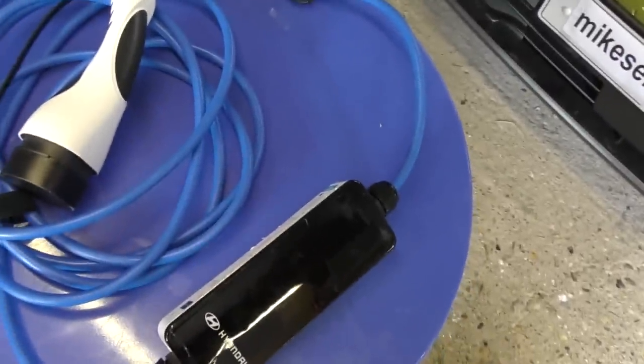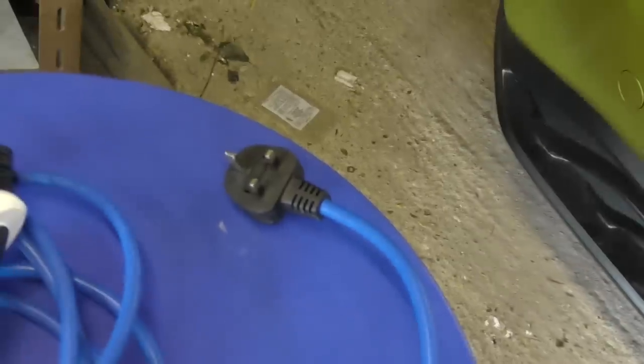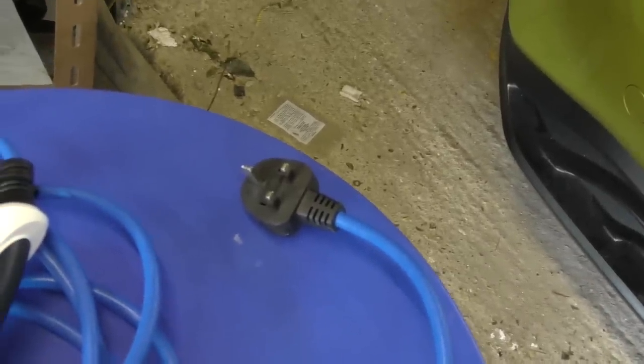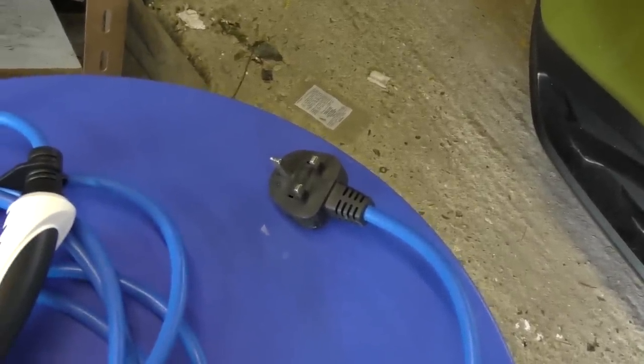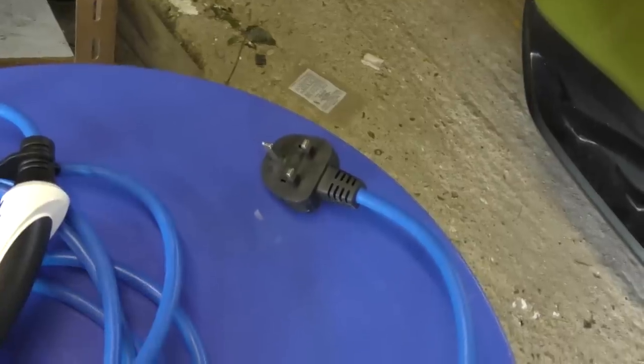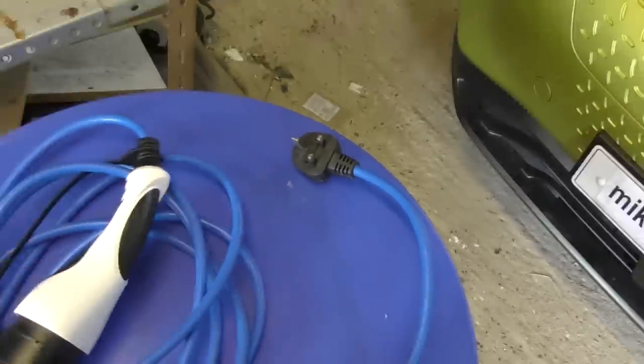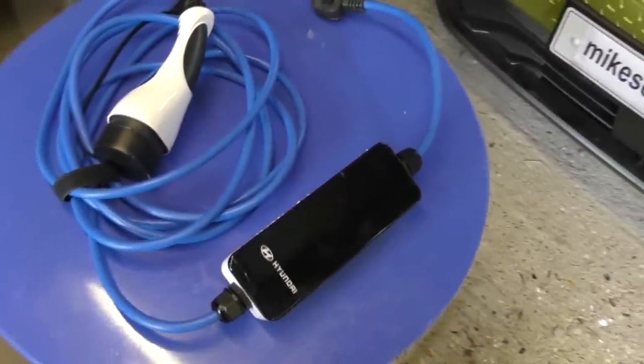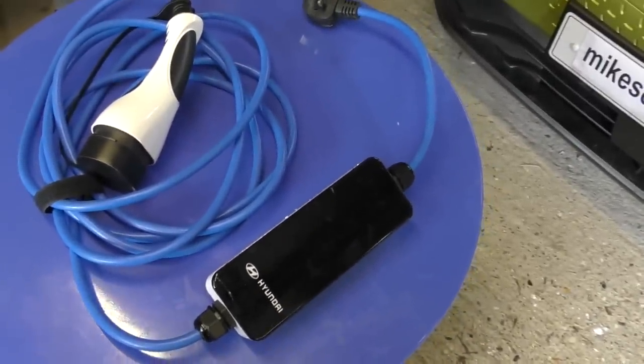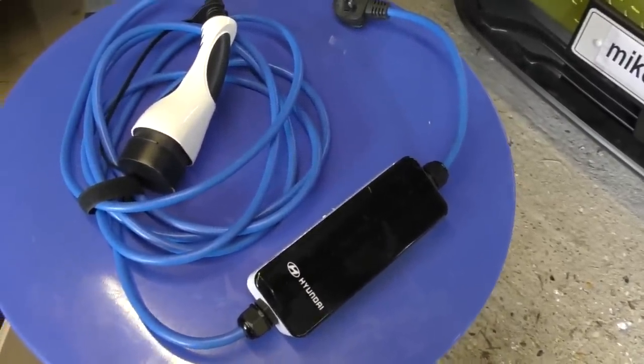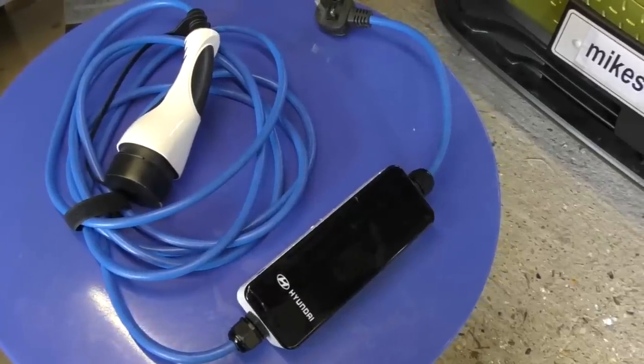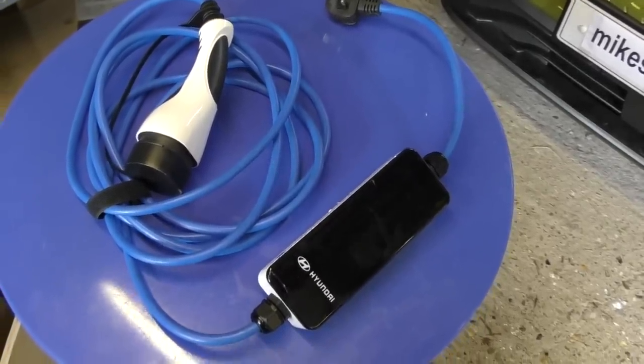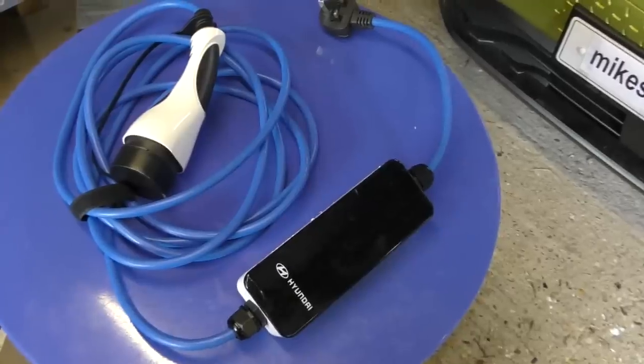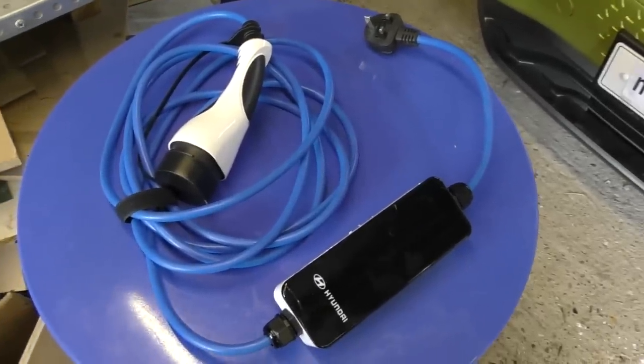And in fact, a lot of the better quality level 1 chargers have temperature sensors inside the plug, so that it can detect, for example, if you've got an old socket that's not in very good condition, that's a potential fire risk. The charger can detect that and shut down if things get too hot. This particular one can also be manually switched from 10 down to 8 or 6 amps. For example, if you're charging where you have a plug that's getting too hot, or somewhere that's got not a particularly good supply, then you can reduce it, and obviously that does extend your charging time, but at least means you can actually charge.